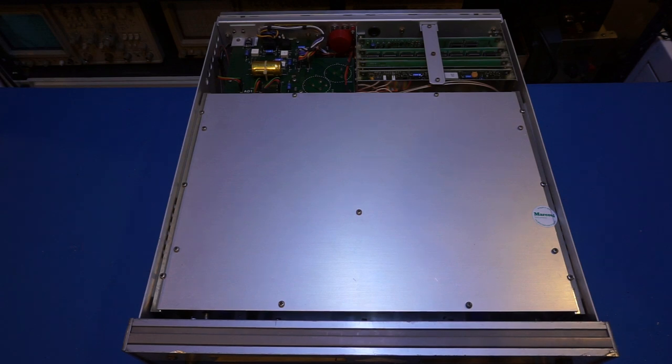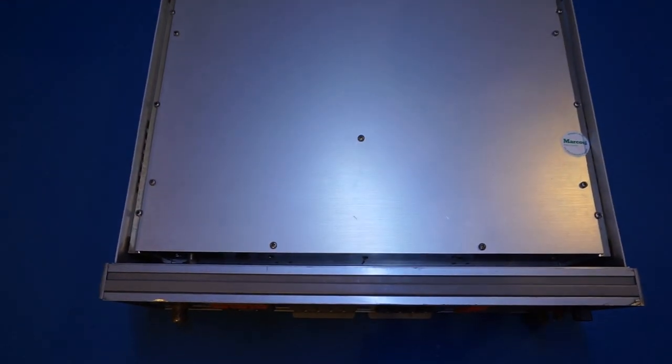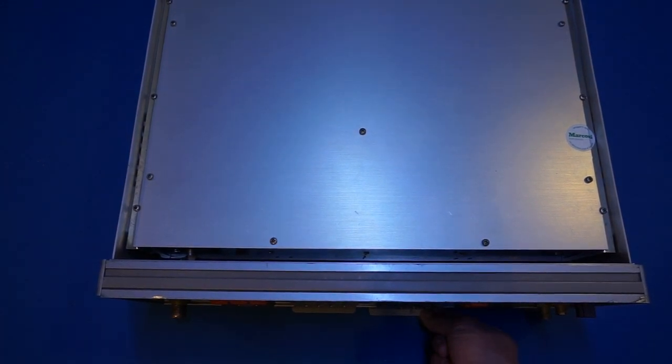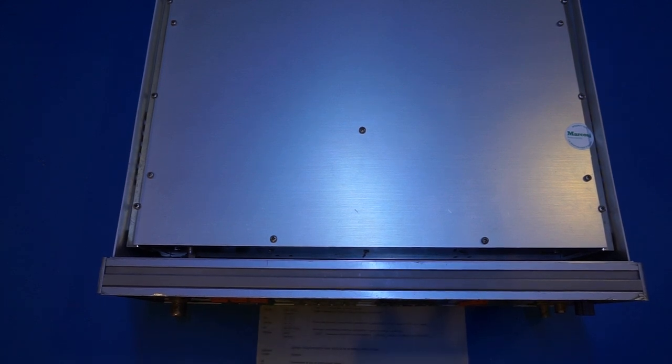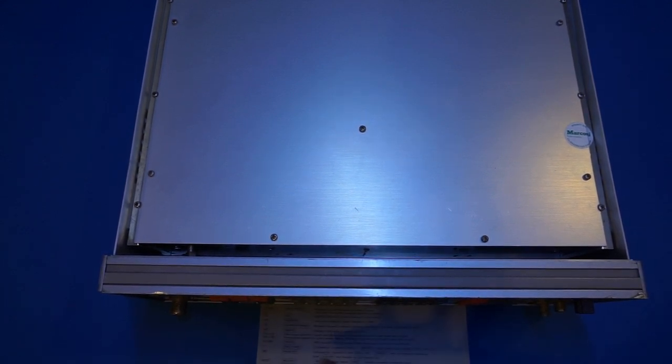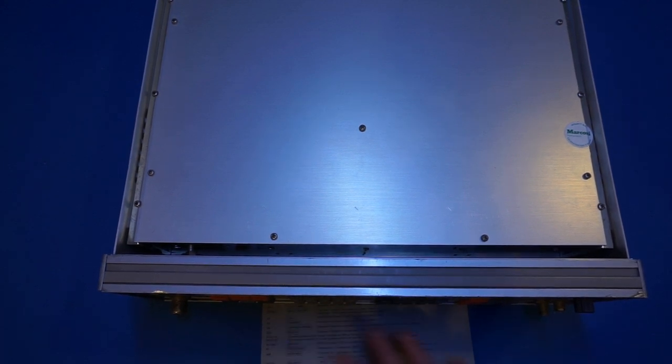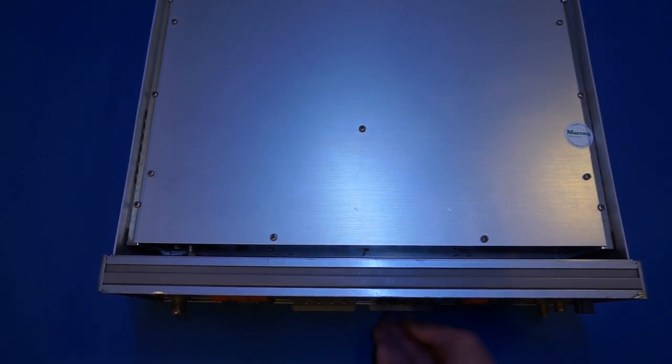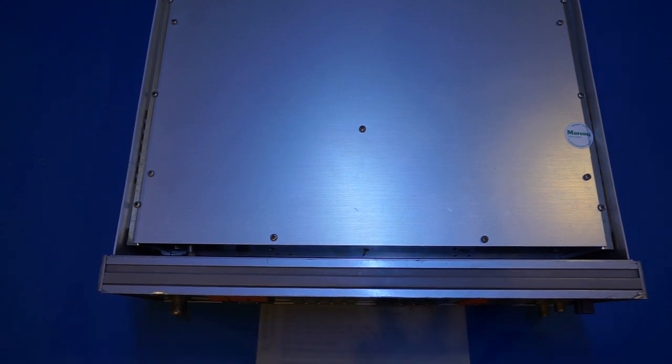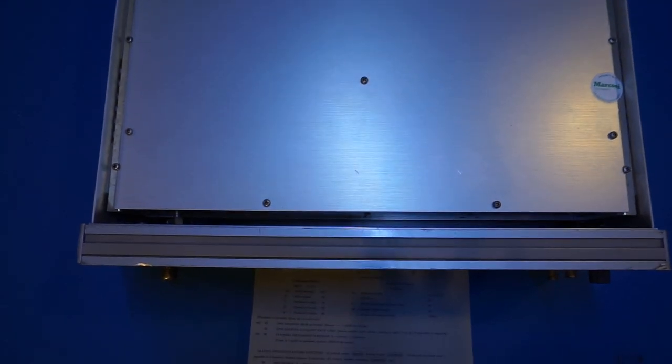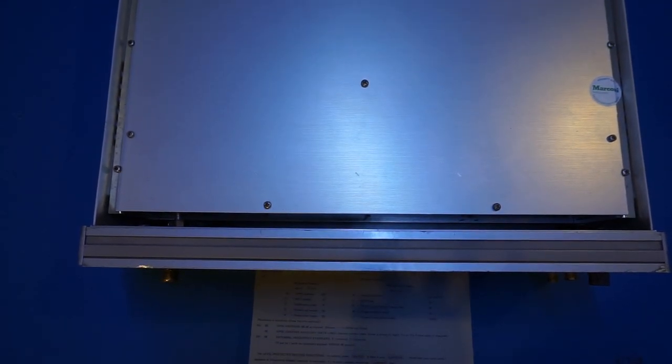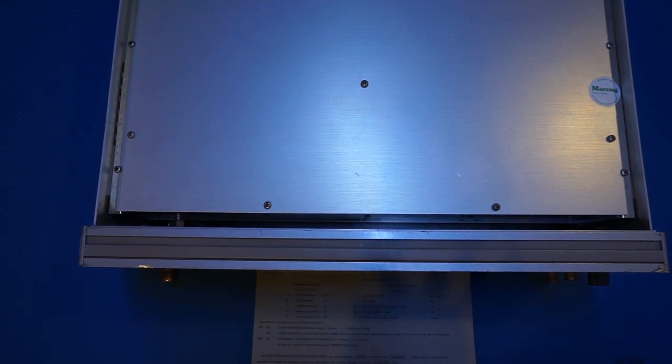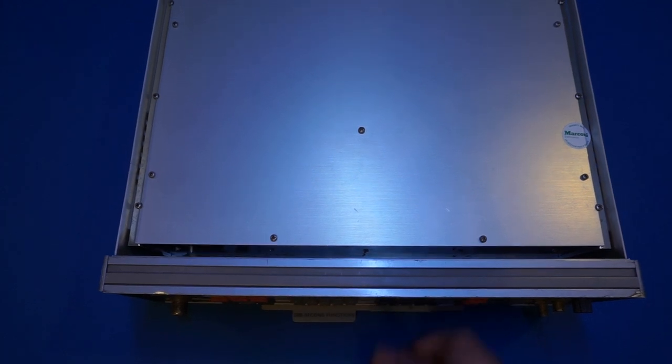Before we continue, let's take a look at what I forgot to mention. These units and quite a few of the HP units also have this feature. We can slide out some of these information cards. For some of the features that you can use on the meter, it's actually laid out on these cards, which is very neat. You don't have to memorize this or have your manual with you all the time. This specific card is for the GPIB and the functionality here.